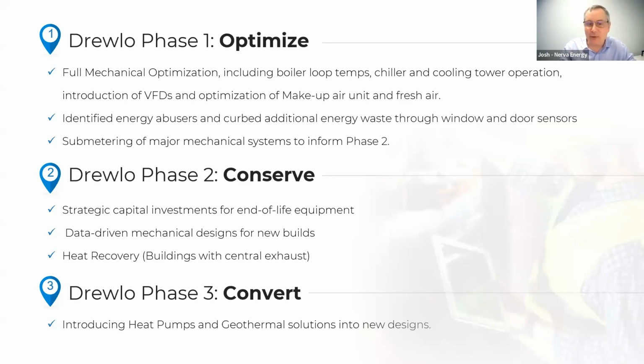And certainly adding heat recovery to buildings with central exhaust. I feel this is a very untapped energy conservation measure. In the Drewlo portfolio, there's not a lot of buildings that have central exhaust, but for any multi-res building in the country with central exhaust, typically on the roof, heat recovery to the makeup air system is one of the most obvious energy conservation measures that should be retrofitted almost immediately.